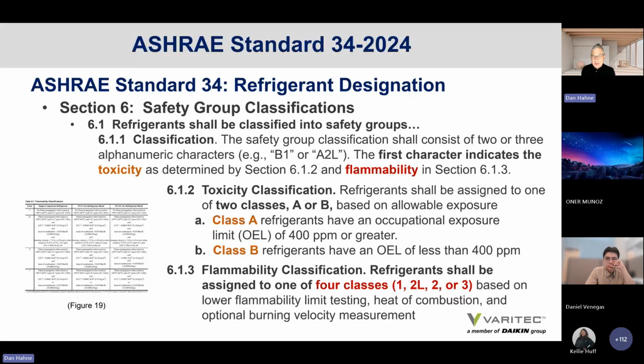6.1.3 assigns flammability classifications. There are 4 classifications: type 1, type 2L, type 2, and type 3. So an A2L refrigerant is a refrigerant that has an occupational exposure limit of 400 parts per million or greater, and it is a class 2L for flammability, which is lower flammability level. So be aware of that. And the characteristics of each of these refrigerants is listed in figure 19 to the left.